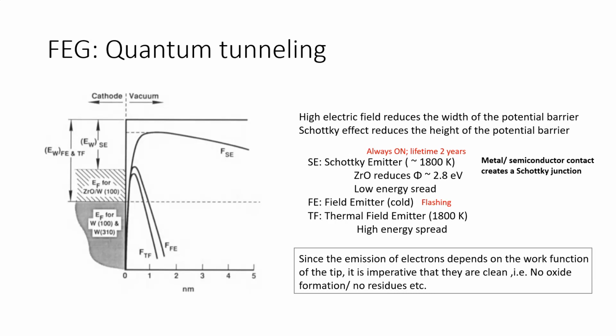So there are three types of field emission guns. One is a Schottky emitter, and we spoke about this in the previous calculation that we did, which is a combination of using the thermionic emission along with an increase in the potential that is applied to the tip to extract these electrons via a combination of thermionic emission and quantum tunneling. The cold field emitter simply uses the field, so there is no temperature involved, unlike the Schottky emitter.